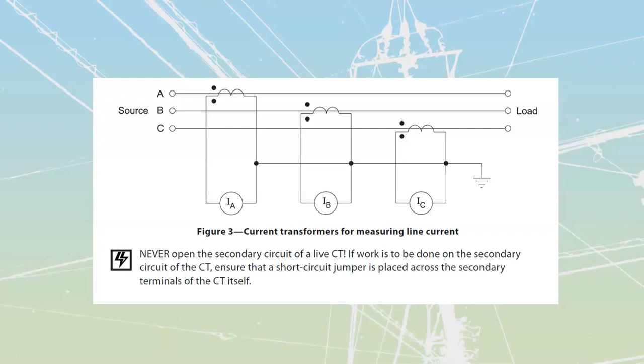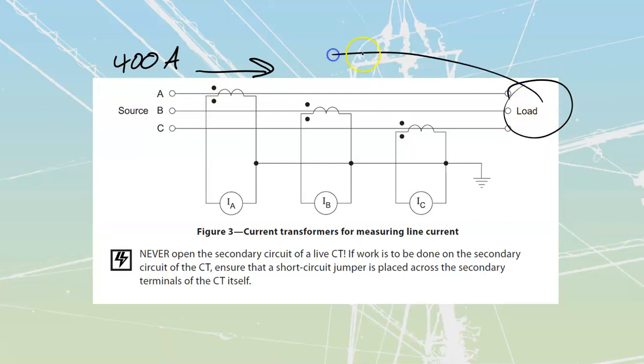In other words, if I've got a 400 amp system over here, that 400 amp system, we're going to have a bus bar that's going to be passing the current through out to my load. So my load down here is pulling current through there, and then I would just have a 400 to 5 transformer over here, a CT. By the way, CTs are always going to be rated current to 5. We're not going to say that it would be an 80 to 1, even though this is an 80 to 1 ratio over here. We would call it 400 to 5 that we have.